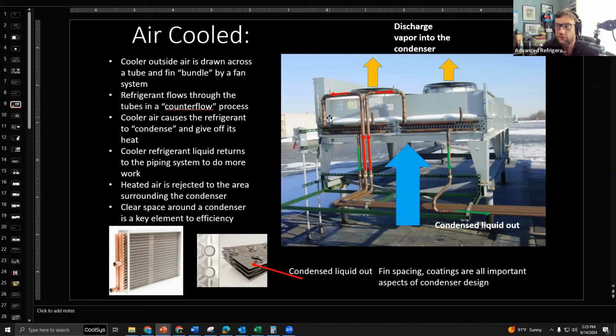So notice, usually when you have even a split system that's on a roof and you have two fans, if they do shut off one of the fans for ambient conditions, the one closest to the header will stay on all the time. The other one, opposing and farther away from the header, is the one that'll be cycling.